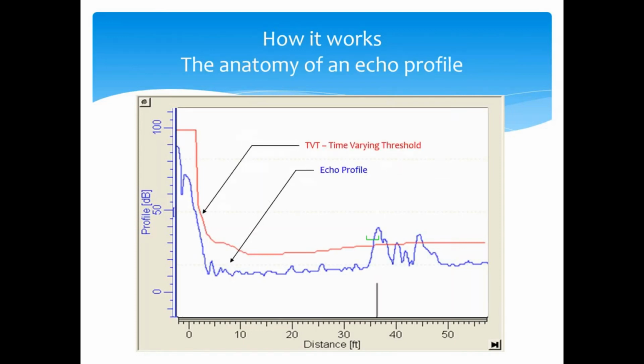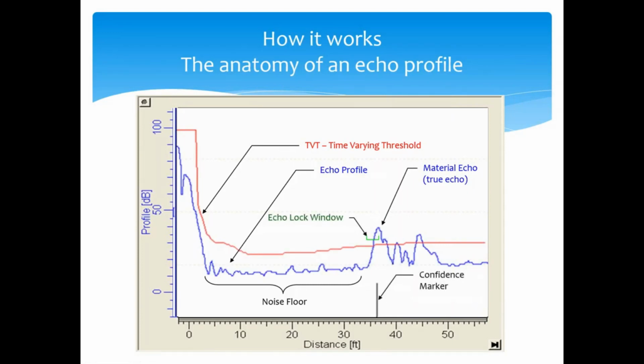So this kind of just talks a little bit about some of the things that I just mentioned. There's your echo profile, your varying threshold, your noise floor. This is our material echo in this case, or true level. The little green box is our echo lock window, so that's always going to show up on true level. And then the confidence marker is just a depiction of the confidence of the instrument. On your display, you'll also have a confidence value, which will be between 0 and 100. The higher that number is, the more the instrument is really in tune and knows that that is the true level measurement for you. And then you have some secondary or indirect echoes, which again, we'll talk about a little bit more later on.